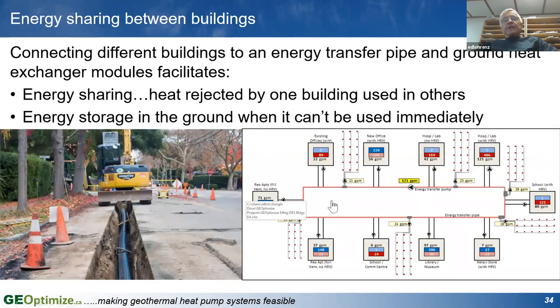The other thing that I'd mentioned earlier was taking advantage of the ability to share energy from one building to the next. And that can be done by simply connecting all of the buildings to one single pipe. Think of it as a conveyor belt to move energy around. This building is actually in heating mode. It's drawing heat from the ground. The building adjacent to it is dumping heat into the ground. So if the fluid is going this way, this one's warming up the fluid, and this one's cooling off the fluid. If that is fairly balanced, we don't even need a ground loop.